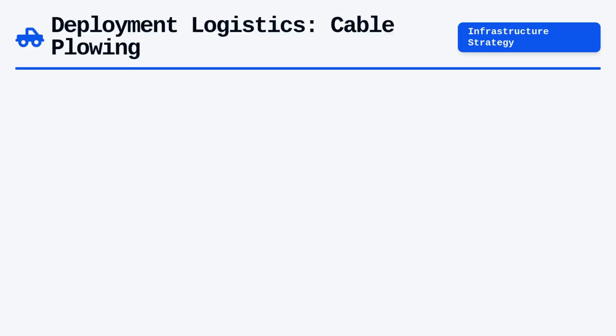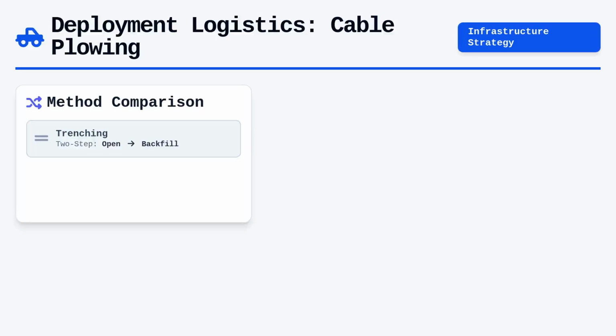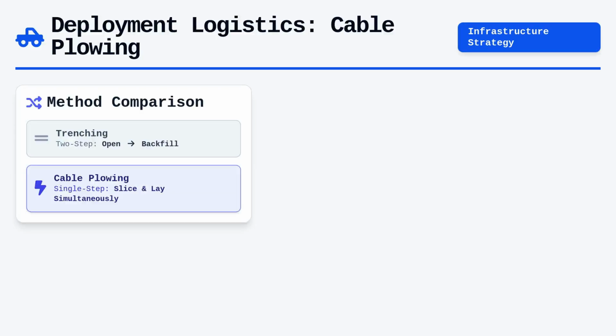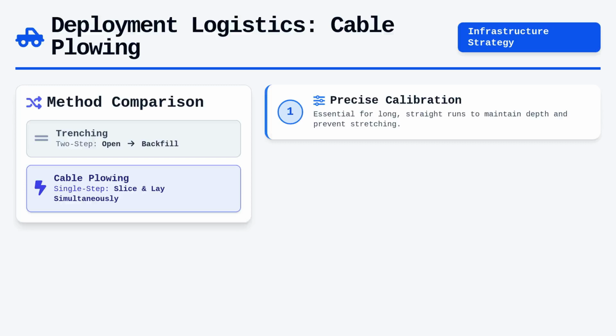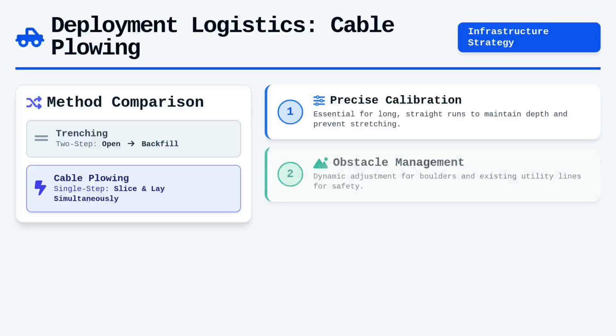Deployment logistics often define the difference between a successful project and a maintenance nightmare, particularly when using cable plowing operations. Unlike trenching, where the ground is opened and backfilled in two distinct steps, plowing utilizes a specialized blade that slices through the earth, simultaneously laying the cable at the correct depth. While this is efficient for long, straight runs, it requires precise calibration to prevent the cable from being stretched beyond its rated pulling tension. Should your route encounter subterranean obstacles like large boulders or intersecting utility lines, the plowing mechanism must be adjusted to navigate safely.